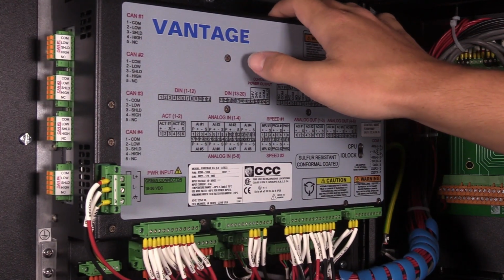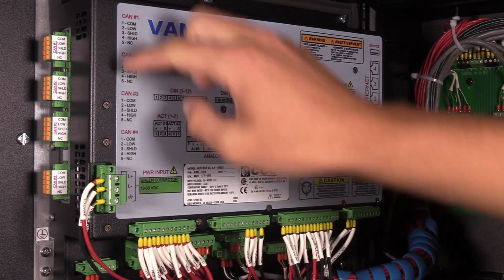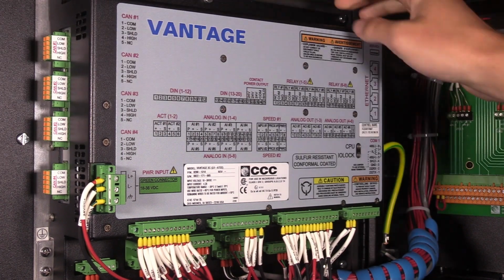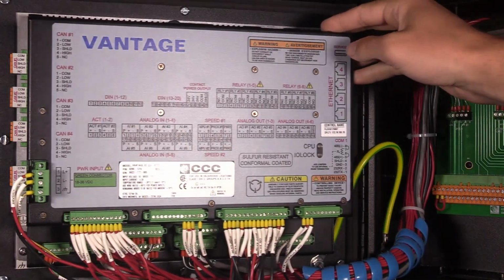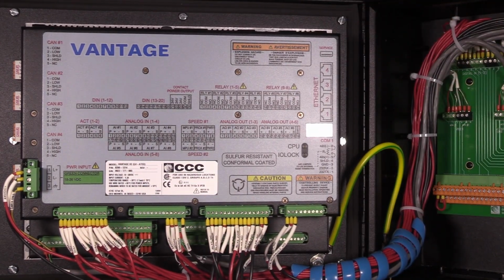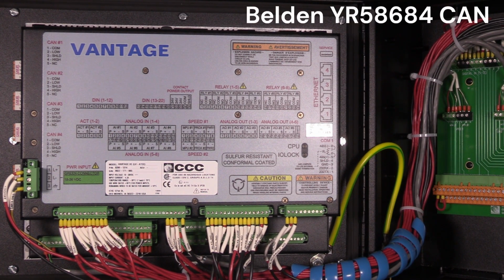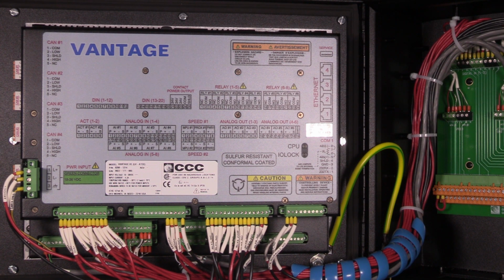Four isolated CAN ports are available for general communications, as well as simplex or redundant distributed control. To wire to the controller's CAN connections, CCC recommends the Belden YR58684 CAN cable or equivalent. This is a smaller and flexible 22-gauge low-capacitance cable, suitable for tight routing in industrial environments.